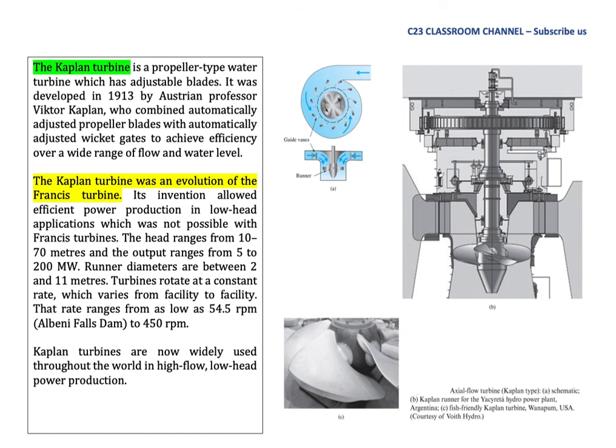Its invention allowed efficient power production in low head applications, which was not possible with the Francis Turbine. The head ranges from 10 to 70 meters and the output ranges from 5 to 200 megawatts. Runner diameters are between 2 and 11 meters. The turbine rotates at a constant rate which varies from facility to facility, ranging from as low as 54.5 rpm to 450 rpm. Kaplan Turbines are now widely used throughout the world in high flow, low head power production.